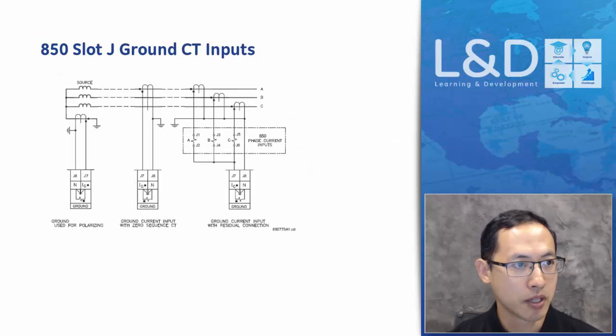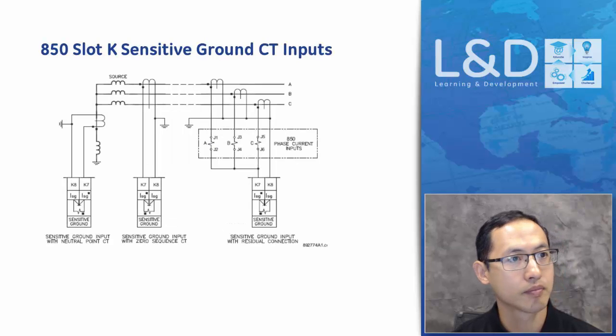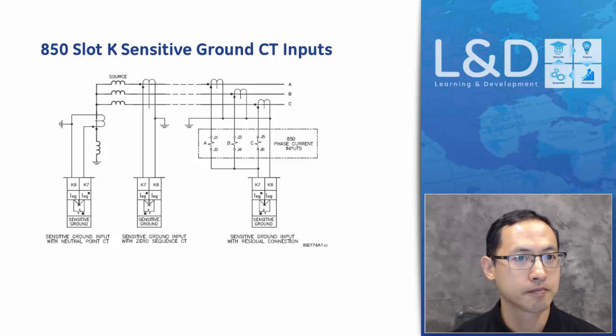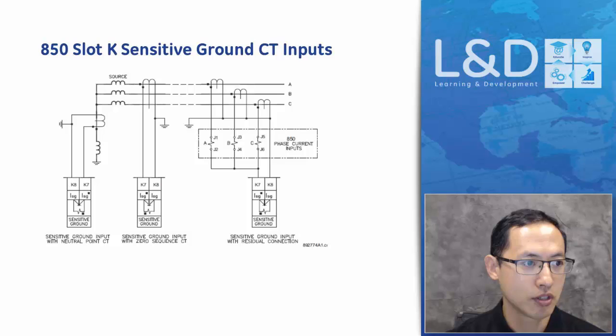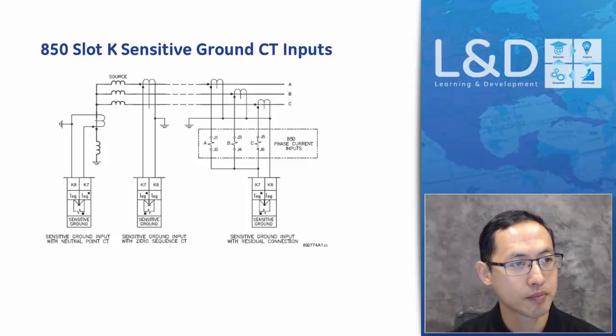For the grounding inputs, it has these 3 types of connections. It can be used from the grounding CTs, or from the zero sequence CTs, or from the residual current from the 3-phase. And if the order code has the sensitive ground enabled, that means you can have an input in the K slot to be used for the sensitive ground input. Again, there are 3 ways for the connections: the direct grounding, the zero sequence CTs, and the residual connections.